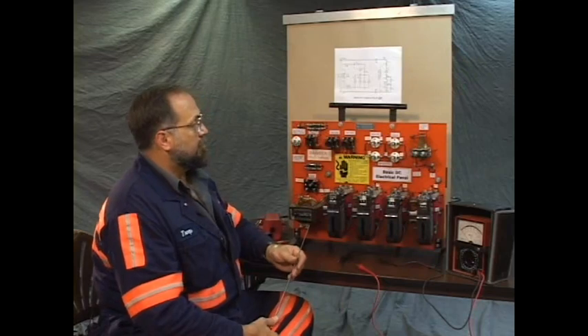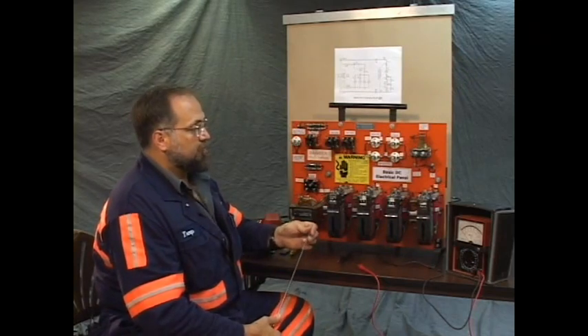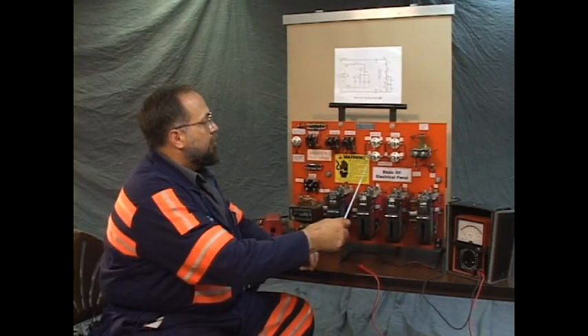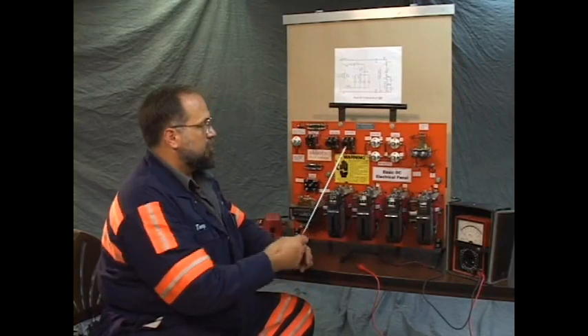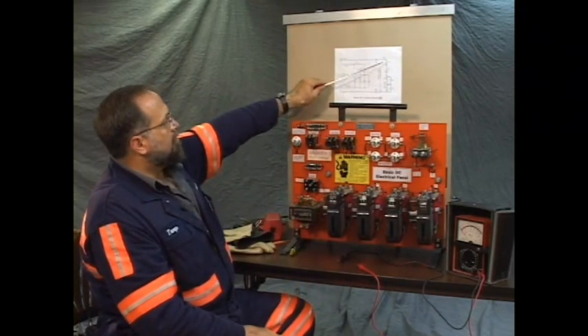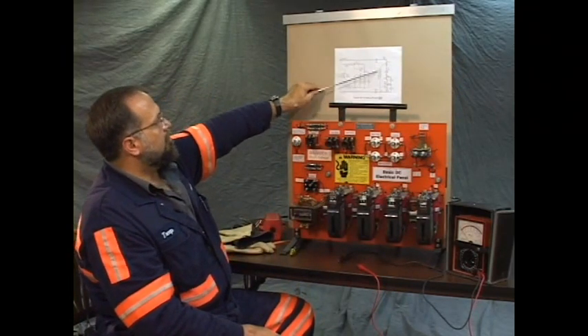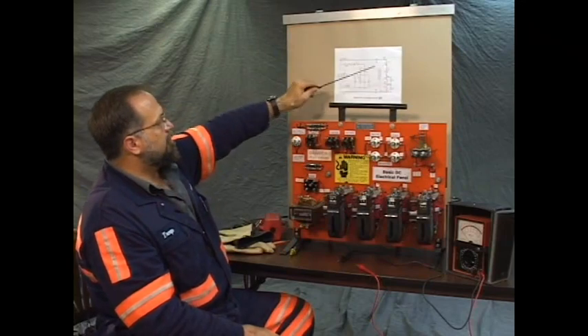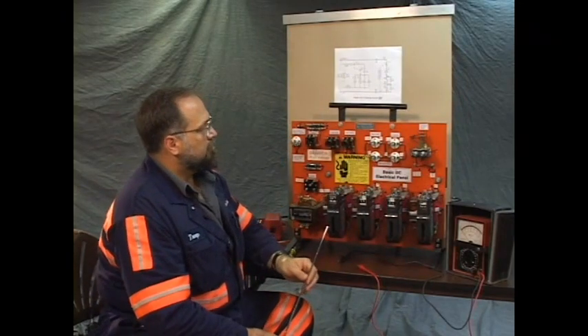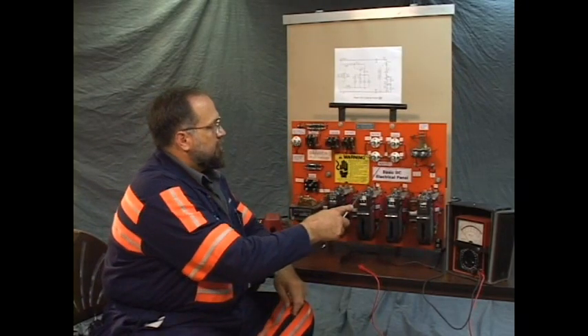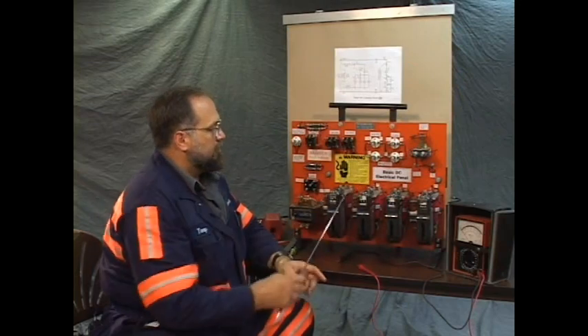The proper sequence of these lights, when you initially start the panel, just as if you were starting a motor: all 4 lights would burn. The shunt field light, because it is alone, in parallel to the rest of the motor, would burn very bright, while these other 3 lights would burn dimly.